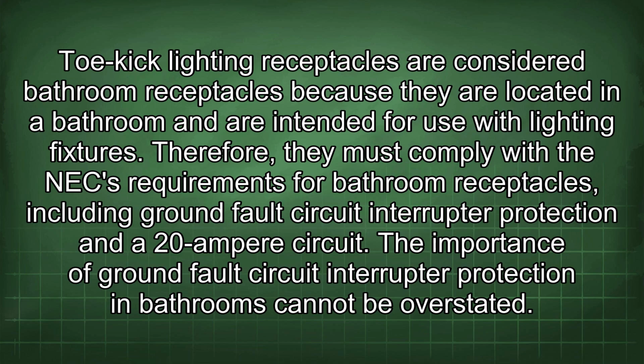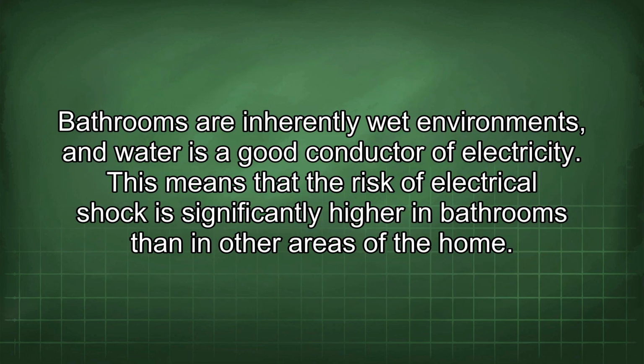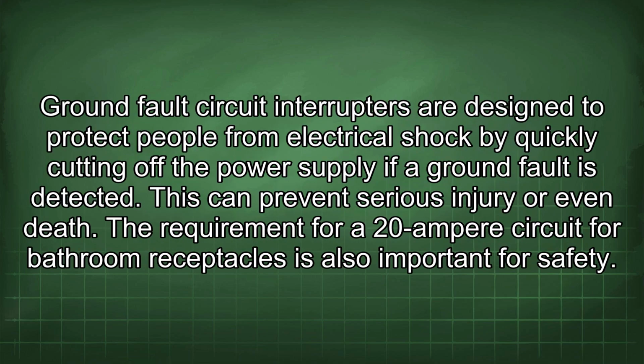Toe kick lighting receptacles are considered bathroom receptacles because they are located in a bathroom and are intended for use with lighting fixtures. Therefore, they must comply with the NEC requirements for bathroom receptacles, including ground fault circuit interrupter protection and a 20 ampere circuit. The importance of ground fault circuit interrupter protection in bathrooms cannot be overstated. Bathrooms are inherently wet environments, and water is a good conductor of electricity. This means that the risk of electrical shock is significantly higher in bathrooms than in other areas of the home. Ground fault circuit interrupters are designed to protect people from electrical shock by quickly cutting off the power supply if a ground fault is detected. This can prevent serious injury or even death.